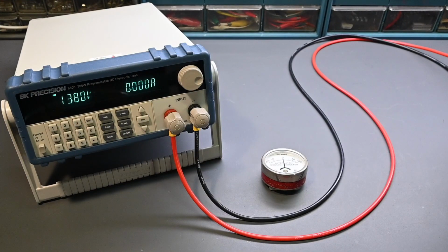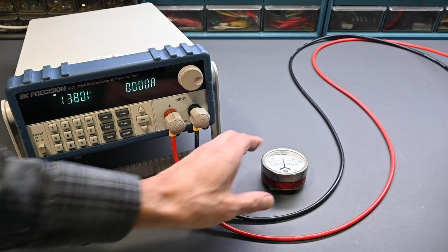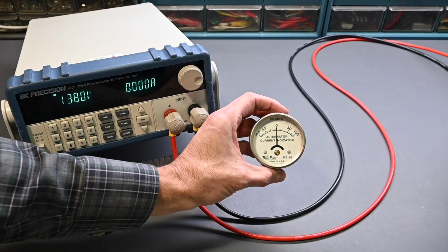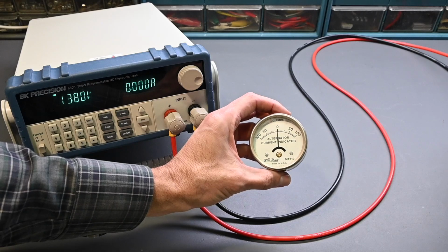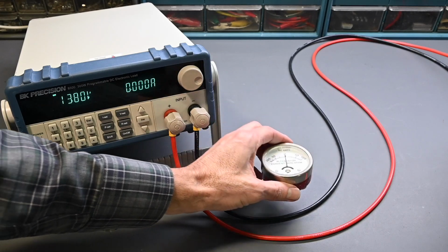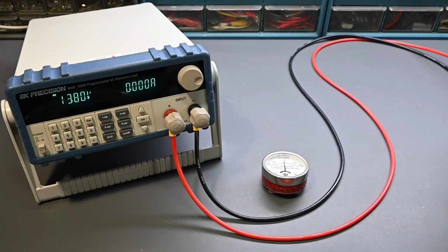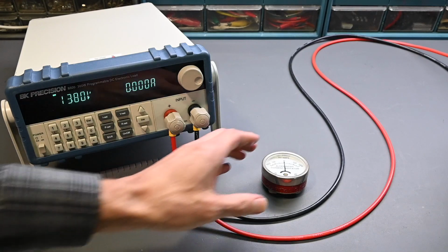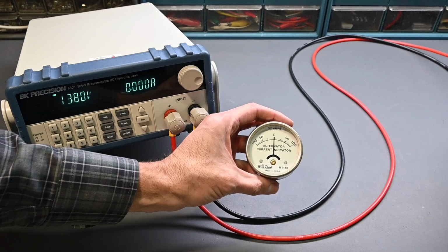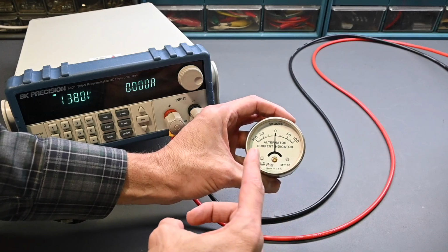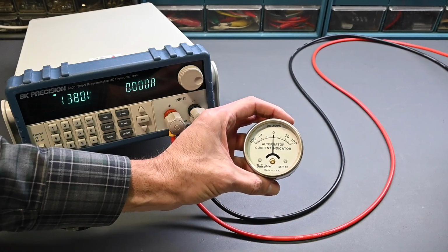So another way to measure current is with an induction ammeter, and that's exactly what this meter is right here. So you can see the center scale sits at 0, and then the left and right scales go up to 100 amps. So an induction ammeter works by sensing the magnetic field around the conductor. It's really only meant for DC current. So AC current would try to swing the needle in both directions, and effectively it would just remain centered. Now if the AC frequency was extremely low, maybe only a few hertz, the needle probably would track back and forth, but again, these are meant for DC current.